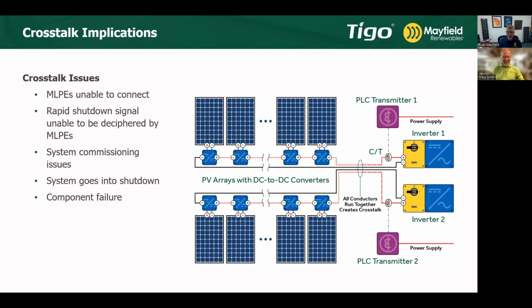But it was interesting because every single inverter individually would start up. We would just turn it on, there were 6 inverters on site, every single one. You turn it on, go through the startup procedure, it worked like a charm. And go to turn on number 2, it wouldn't turn on. Number 3 wouldn't turn on. But shut down number 1 and turn on number 2 by itself, not a problem.